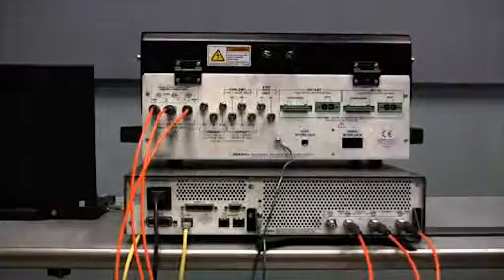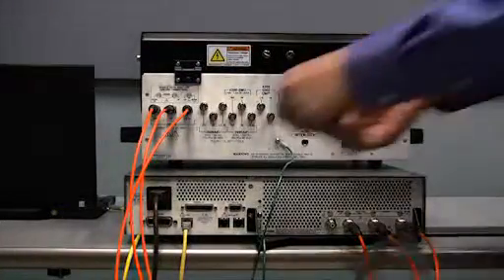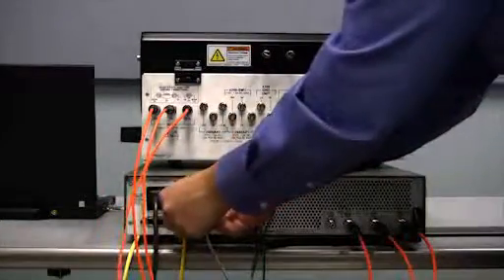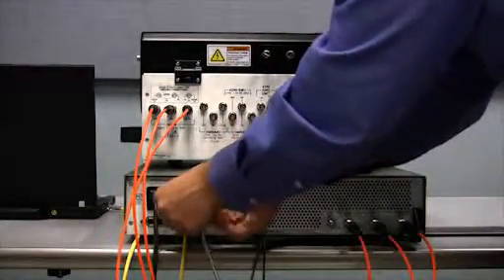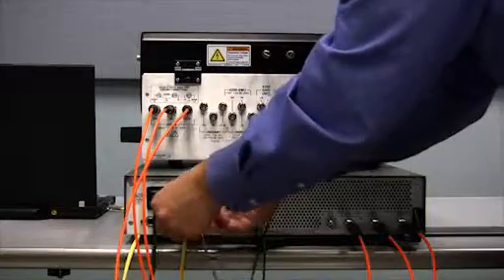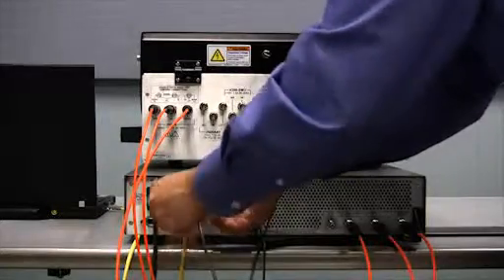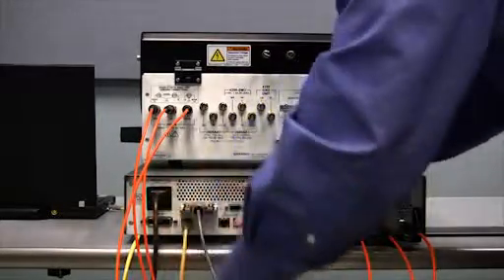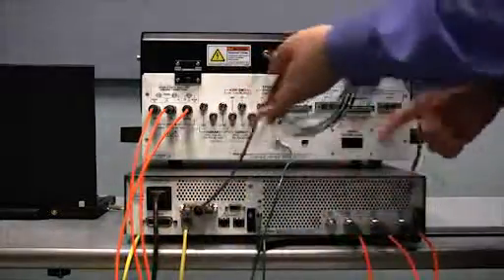Second, connect the interlock cable from the digital I.O. port of the model 2657A to the interlock input connector of the model 8010.